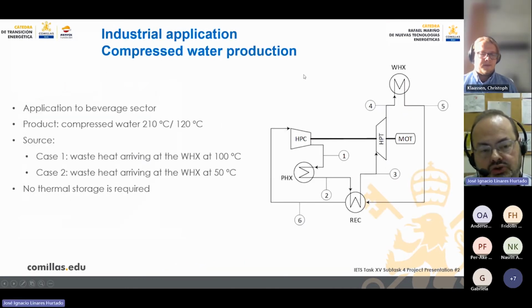And now let me show two real industrial applications. One is to produce compressed water. As you can see here, in this case, no thermal storage is required, so we have put the product heat exchanger at the outlet of the compressor, high pressure, and the application may be in the beverage sector, for instance, in a beer factory. The product is compressed water from 210 Celsius degree to 120 Celsius degree at enough pressure to be liquid.